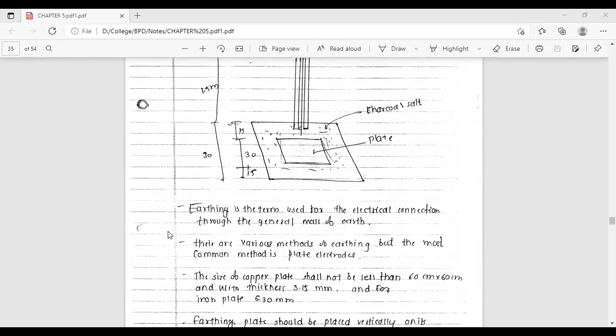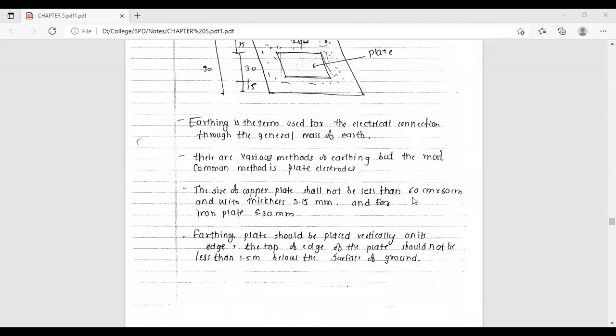Okay, the size of the copper plate shall not be less than 60 centimeter by 60 centimeter with a thickness of 3.15 mm, and for an iron plate we have to use a plate thickness of 6.30 mm. The earthing plate should be placed vertically on its edge. The top edge of the plate should not be less than 1.5 meter below the surface of the ground.